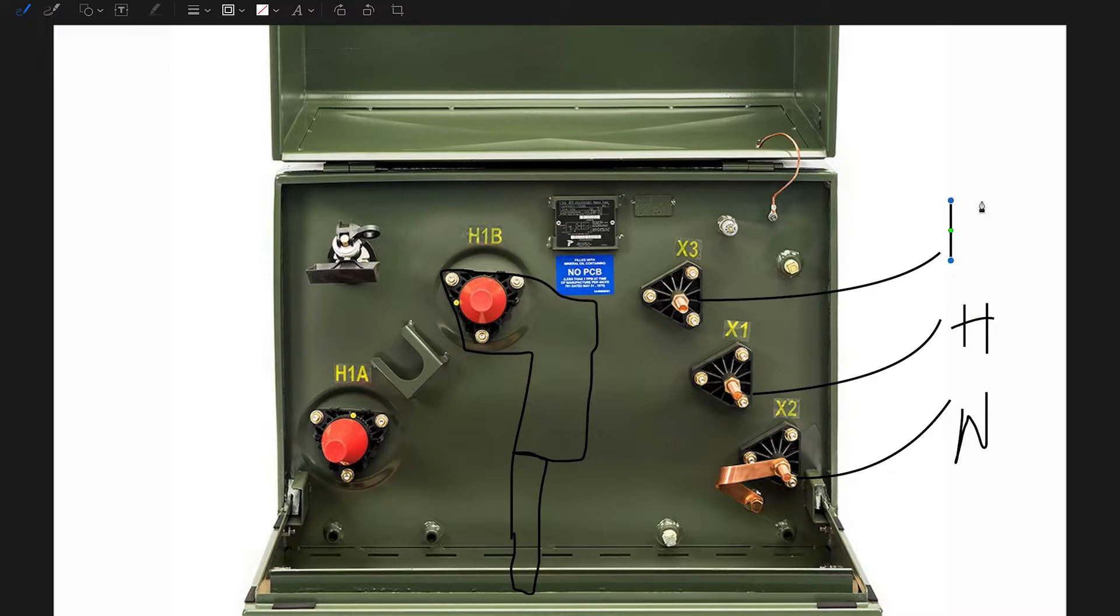So you have two hots and a neutral. Between the hot and the hot, you're going to have 240 volts. And then between the hot and the neutral, you're going to have 120 volts.